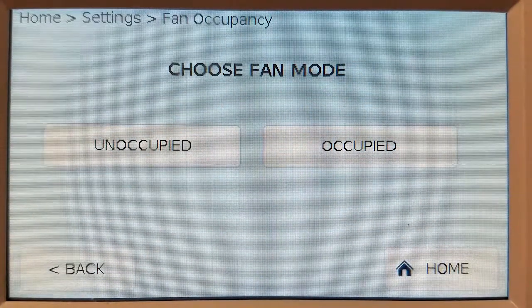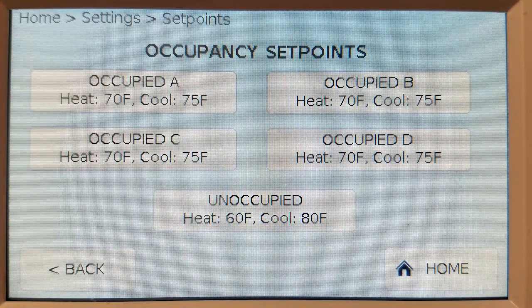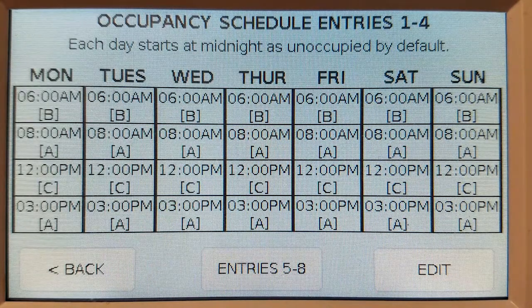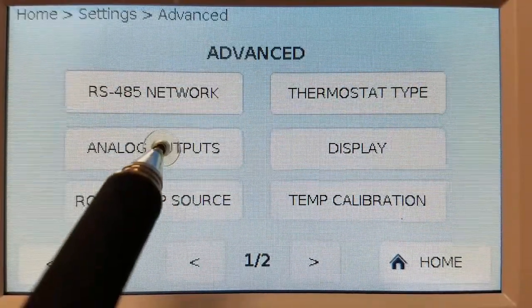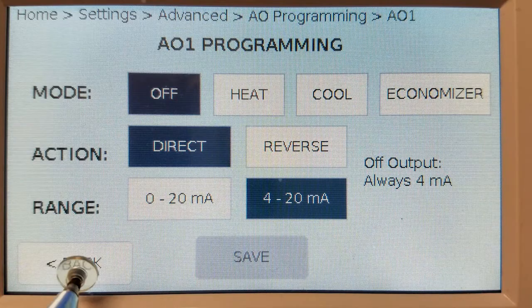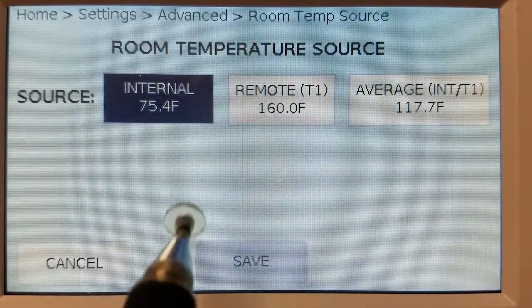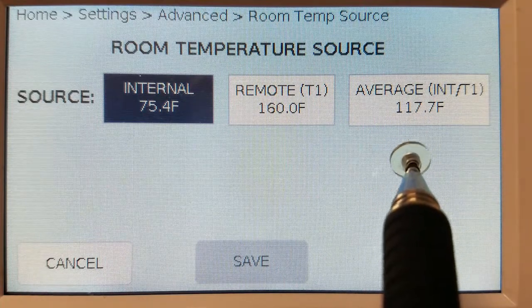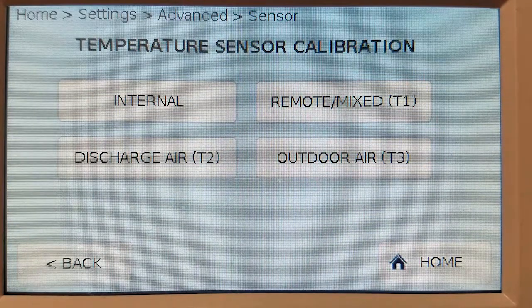Easily configure both occupied and unoccupied fan and system modes, up to four occupied sets of heating and cooling set points, and a seven-day schedule with up to eight different changes throughout the day. Advanced features let you configure the analog outputs by selecting the mode, action, and range. Room temperature source lets you choose the internal sensor, a remote sensor, or an average of both. You can also easily calibrate remote sensors if needed.